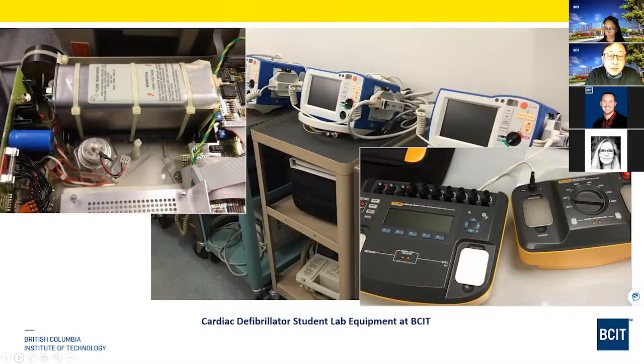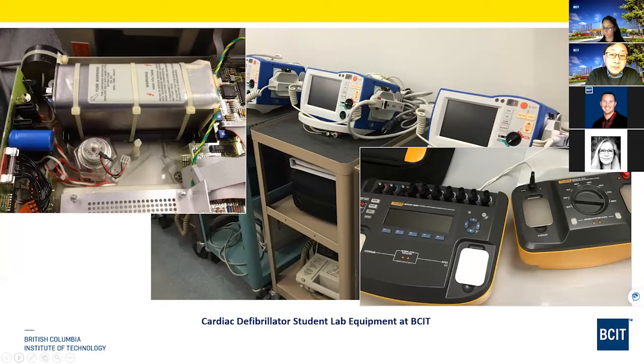These are some of the equipment in our labs. These are defibrillators — the kind often seen on TV or in movies where someone has a cardiac event and the paramedic tries to defibrillate the heart. In our program, we teach students the principal operation of this device technology — for example, how this device can reverse the heart condition from fibrillation to a normal heart rhythm — and also look at the technology used to deliver voltages or current to the patient, the component construction of the devices, and how to carry out performance assurance to make sure these devices are working properly in the field.